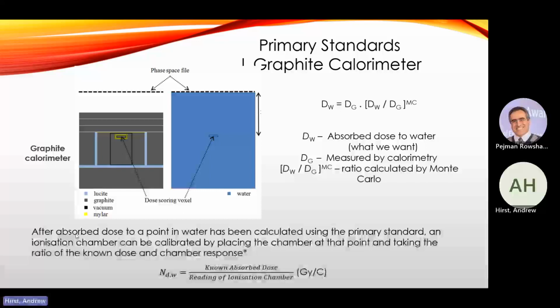So finally, after we have absorbed dose to water defined at a point, and it's been calculated using this primary standard of high metrological quality, we can place an ionization chamber at the same point and take a measurement of that same amount of total energy that you just gave the calorimeter. So that could be measured in time, for example, if you had a cobalt 60 unit. I'm not too sure if you guys have learned about cobalt 60 units and linacs. But a cobalt 60 unit basically just has a real actual radioactive source in it that's constantly emitting radiation, so you would measure it in time.